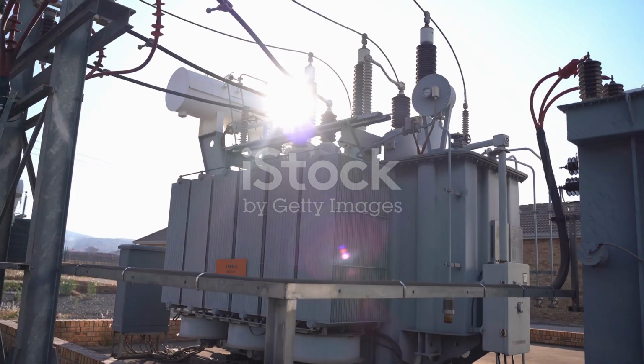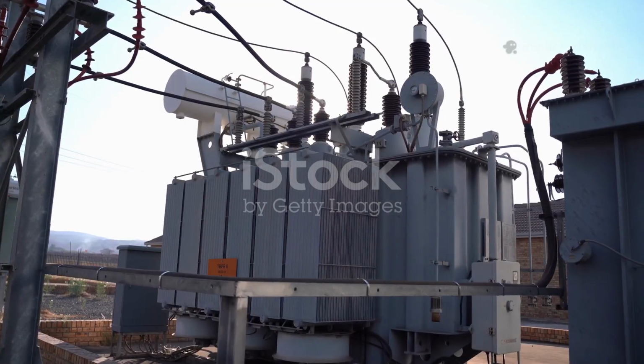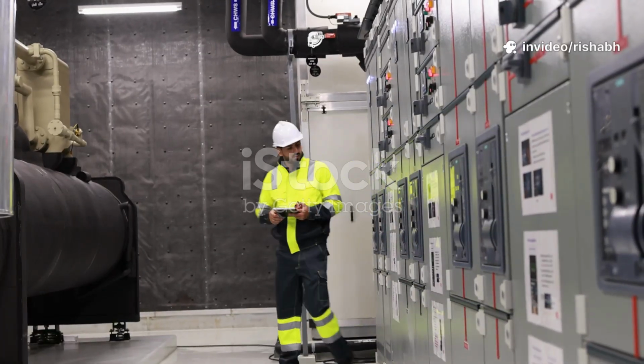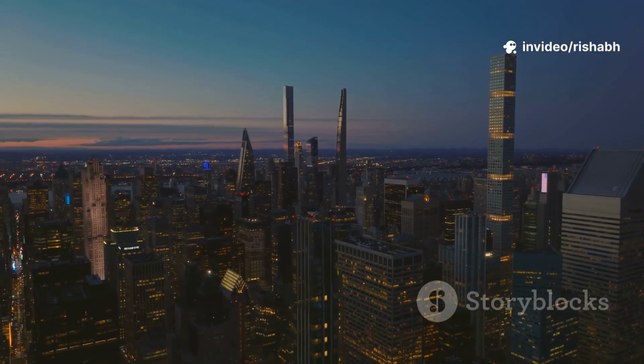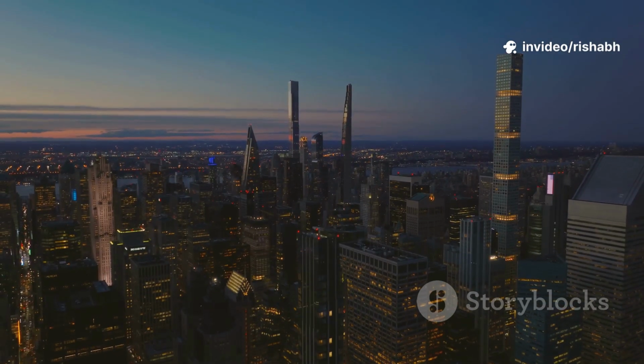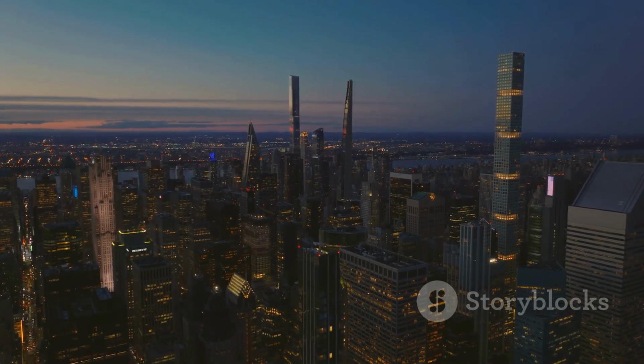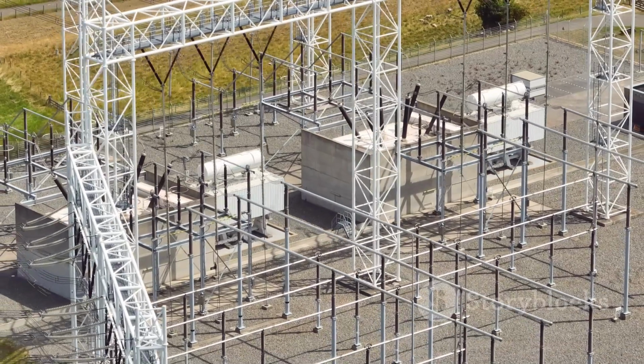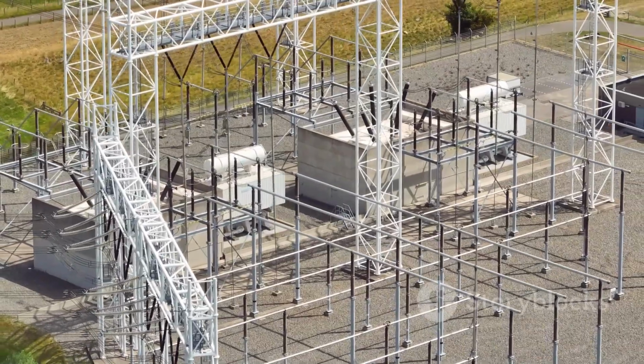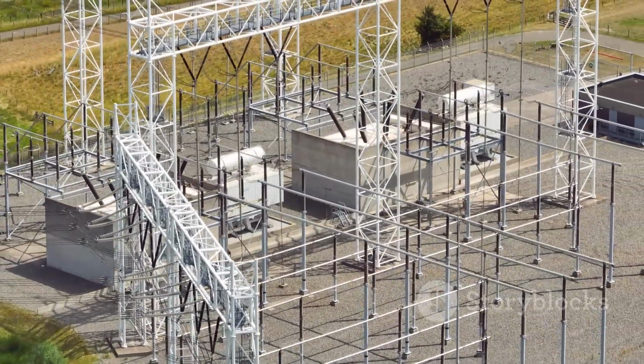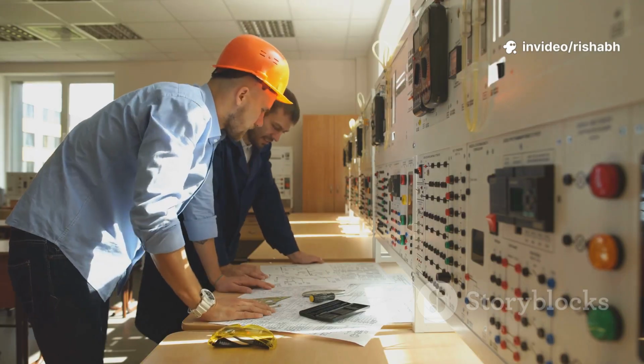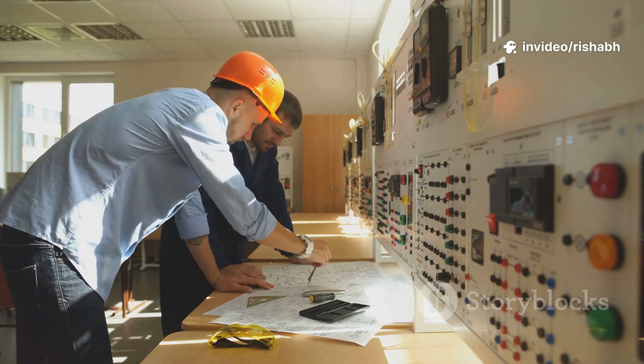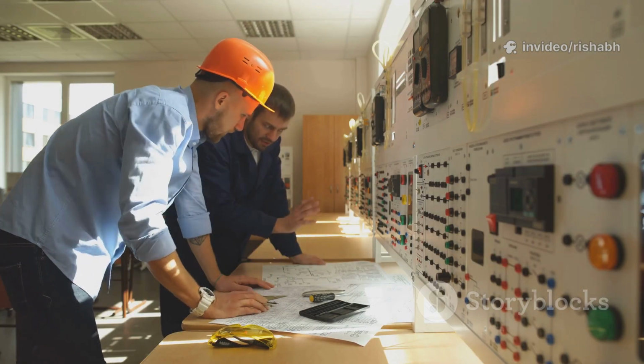A transformer's voltage ratio is determined by the number of turns in its windings. But what if we need to adjust that voltage? The load on the power grid is not constant. It fluctuates throughout the day and night. As demand changes, voltages across the network can sag or swell. To maintain a stable voltage supply for consumers, we need a way to fine-tune the transformer's ratio.